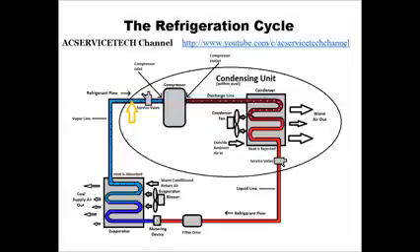If you took it from right in the middle of the evaporator coil, right after the saturated state where it turns into a complete vapor, the temperature increase from there all the way over to the service valve next to the compressor is called the total superheat. After that, it just enters back into the compressor as a low pressure, low temperature vapor refrigerant, and the refrigerant cycle starts all over again.